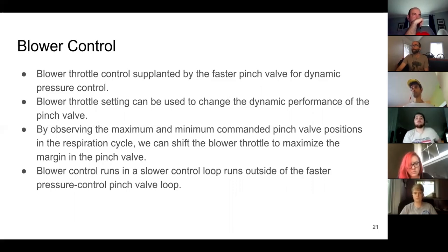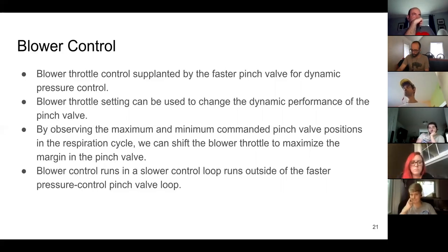This is essentially just a skeleton concept of operations for the blower control. We know that we won't need the blower to respond instantaneously, right? It's no longer critical for the real-time pressure control of the breathing loop. However, there's still some performance we can gain by controlling the blower.